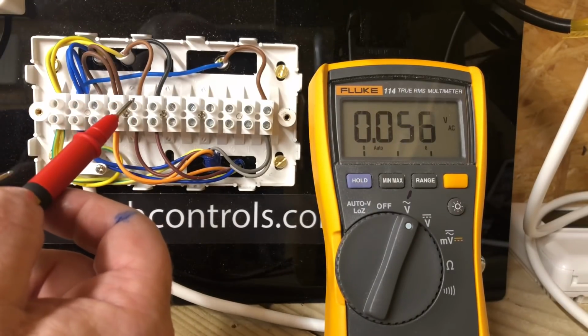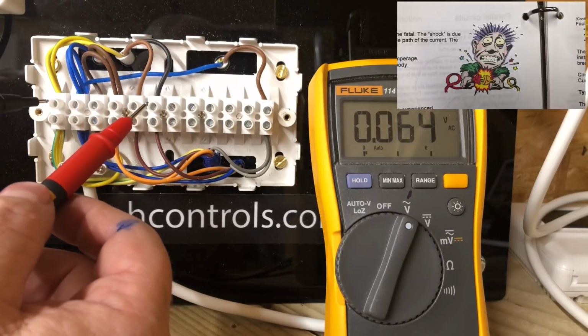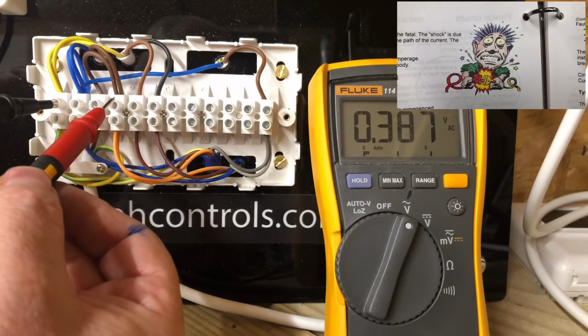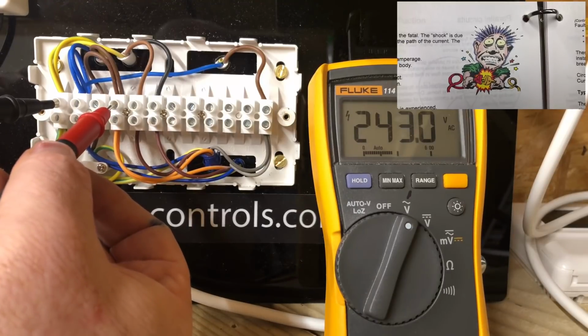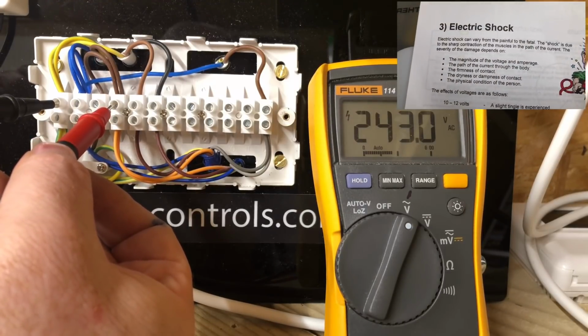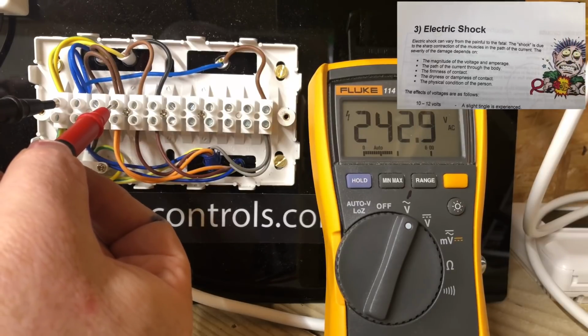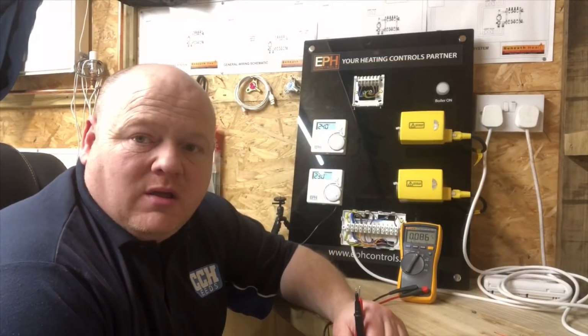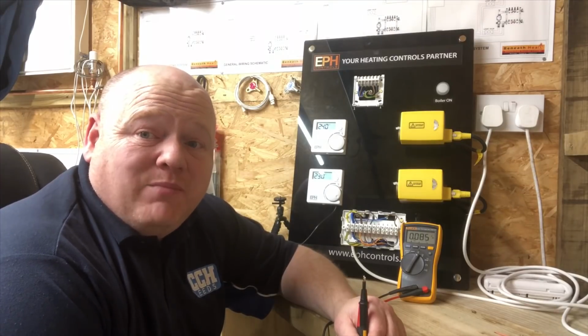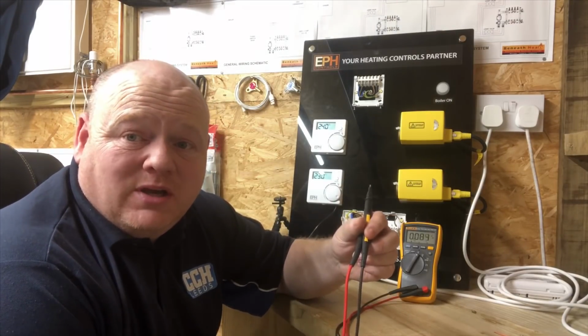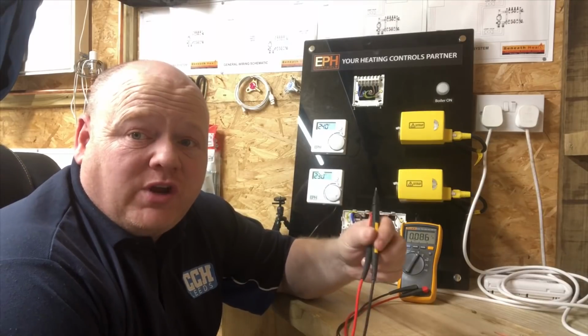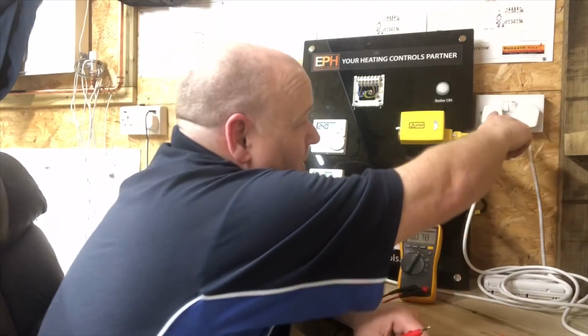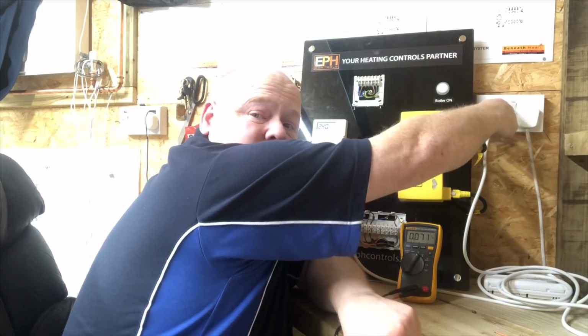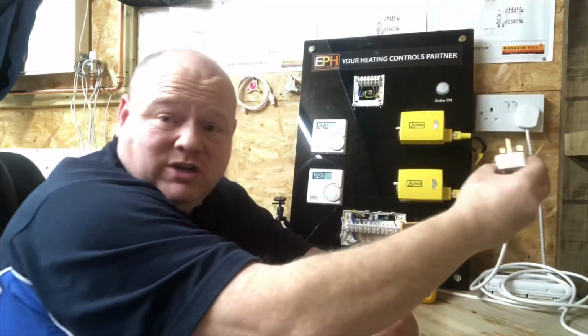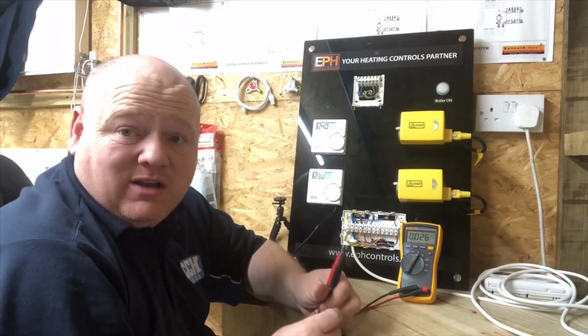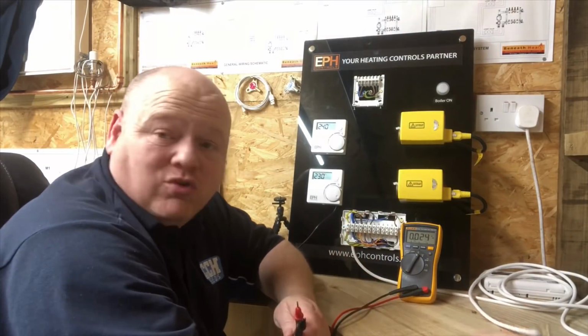But this is what I want to show you about correct isolation and safe isolation. If we now check on there, we can see we've still got 240 volts. Now I'll show you the reason for that. That couldn't have happened at a better time really, because I'm testing it out with the multimeter, and this is no trick. What's actually happened is the switch on here is faulty, and that's why it wasn't isolated.